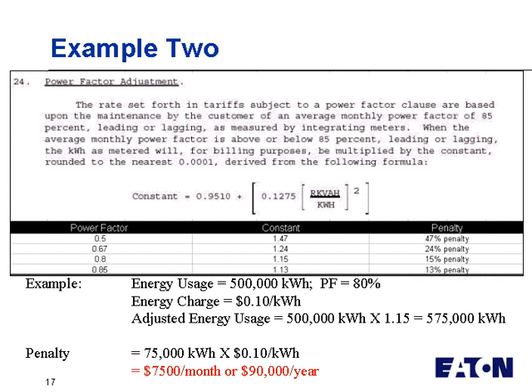Here's another example, and if you can read the, again, fine print, basically this one says that the kilowatt hour charges are going to be adjusted by a certain value if you actually have lower than, in this case, 85% power factor. And if you can see down below, they say, for example, on our example here, we use the power factor of 0.8, and we have 500,000 kilowatt hours usage during that month. We would say that for a 0.8, the multiplier is 1.15, or a 15% penalty.